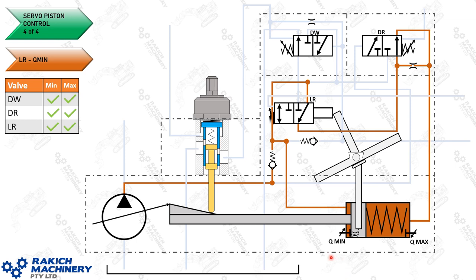Here we're showing the LR activated in a very simple form. We've got high pump pressure in this phase. The high pump pressure traveling up through here is sent to the left-hand side of the servo piston. Because the LR valve has moved to the left, this oil gallery running past it is now traveling through this part of the spool, through your DR which is inactive, and into the right-hand side of the servo piston — forcing the pump to Q-min. I'll explain more detail on how the LR works in a few extra slides.